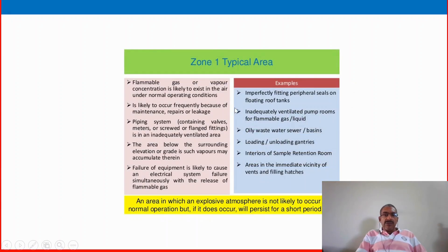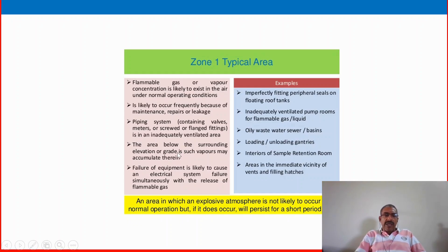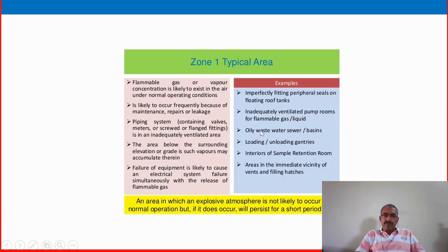Zone 1: flammable gas or vapor concentration is likely to exist in the air under normal operating conditions, slightly over 1.5 meters radius from Zone 0. It is likely to occur frequently because of maintenance, repair or leakage. Piping systems containing valves, meters or screwed or flanged fittings in an inadequately ventilated area. Areas below surrounding elevation or grade where denser vapors may accumulate. Failure of equipment is likely to cause an electrical system failure simultaneously with the release of flammable gas.